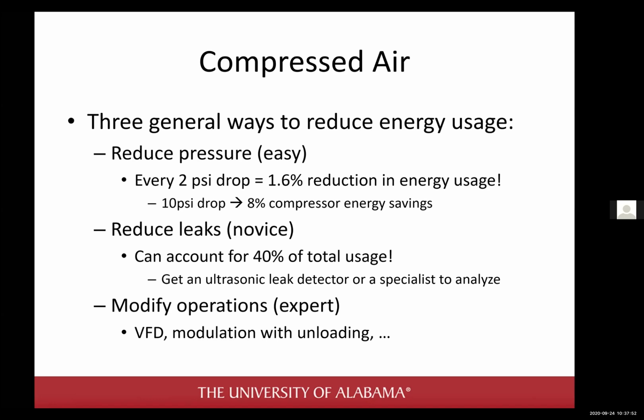And so if you have a period of downtime and your compressor is making air, then you can pretty easily tell that all the power going to your compressor during that downtime is going to feeding leaks. It says in this slide leaks can account for 40% of total usage. Yeah, that's true. I've seen up to 60 or 70% of all energy going to compressors just going to feeding leaks. I don't know why, but with compressed air people just turn the compressor on, they say, well, we need air, that's what we need. But I've seen air receiver tanks after the compressor and the dryer and the filter. You have this big receiving tank usually. I've seen a blower, a hose with a nozzle, and an 1/8 of an inch hole in that. This one tiny hole that was just leaking air was wasting this one company thousands of dollars a year. And all they had to do was just repair a hole in a hose.